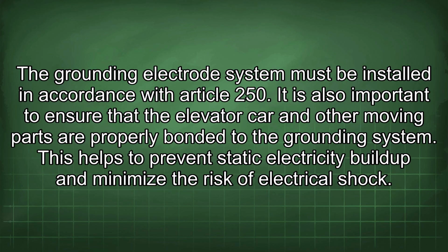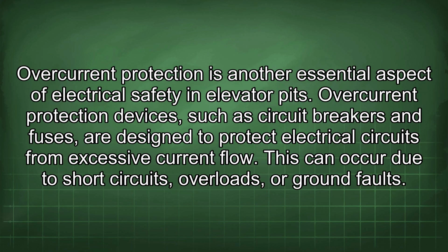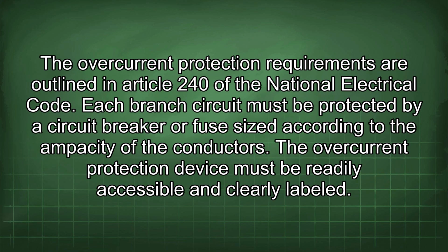It is also important to ensure that the elevator car and other moving parts are properly bonded to the grounding system. This helps to prevent static electricity buildup and minimize the risk of electrical shock. Overcurrent protection is another essential aspect of electrical safety in elevator pits. Overcurrent protection devices, such as circuit breakers and fuses, are designed to protect electrical circuits from excessive current flow. This can occur due to short circuits, overloads, or ground faults. The overcurrent protection requirements are outlined in Article 240 of the National Electrical Code.